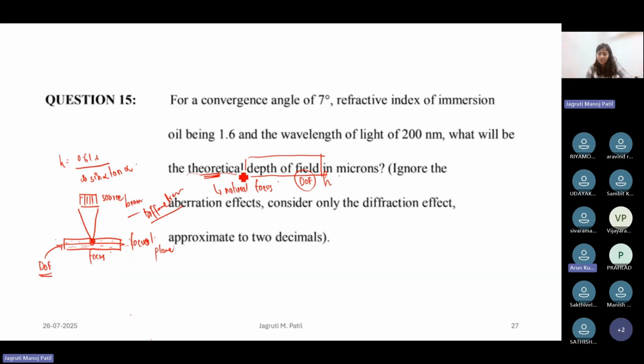That is why this is always theoretical. Let's just say my imaging system's natural focus is around 8 mm, and if I am forcefully trying to image at 4 mm, it won't be that focused, and the image will get somehow blurred, but you'll be able to see the features that you want to analyze. But it would perform at its best resolution, what the system or the company claims, only at its natural focus, only when you are within this depth of field.